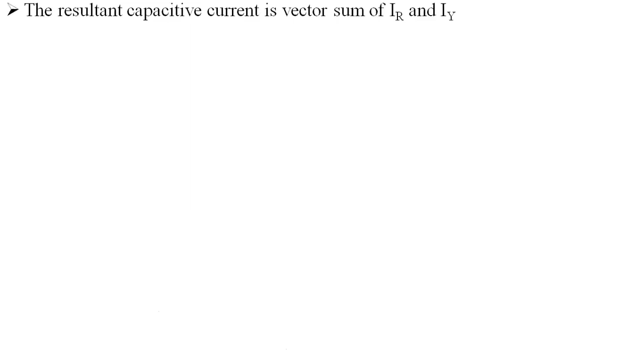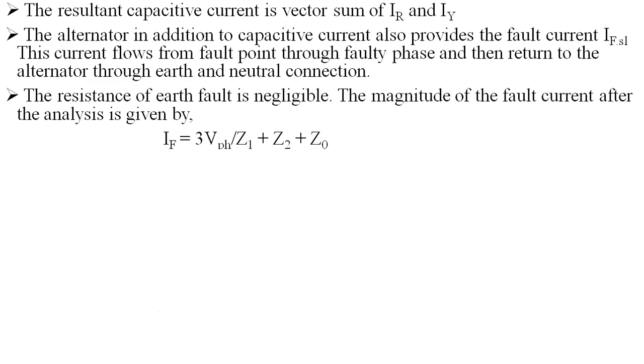See, the resultant capacitive current is the vector sum of IR and IY, and the alternator in addition to this capacitive current also provides the fault current IF1, and this current flows from the fault point through the faulty phase and then returns to the alternator through earth and the neutral connection. And the resistance of this earth fault is negligible, and the magnitude of the fault current after the analysis is given by: the fault current will be 3 times the phase voltage divided by the sum of the positive sequence impedance, negative sequence impedance, and zero sequence impedance.